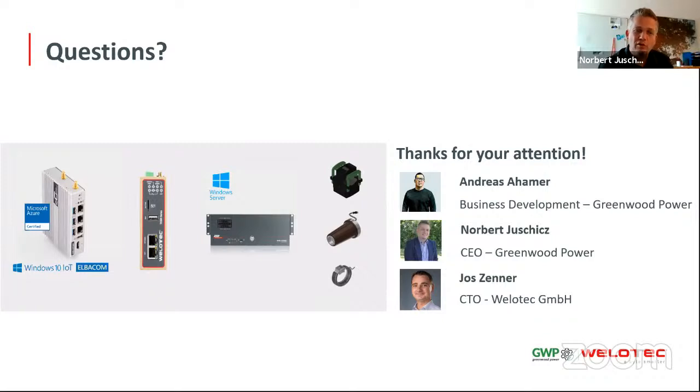If we go down to the low voltage area, it might make more sense, to be honest, because on the low voltage side, the biggest use case is load management. So in this use case, you don't need to have the values every second. It's enough to have them every 15 minutes. So in this case, it could be enough to have just 3 current sensors there to send the data digitally every 15 minutes, and it doesn't matter if they are synchronized or not. Yeah.